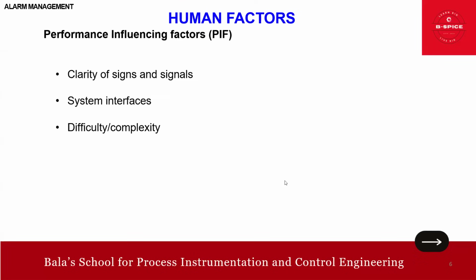Then we have difficulty and complexity. Spending time during HMI design to simplify operator response will increase the likelihood of successful response. So difficulty and complexity we need to take care of. Then time available versus time required. Ensuring early detection increases the time available to diagnose and respond. Providing easy access to information in a useful format reduces the time required to diagnose and respond, isn't it? Yes.